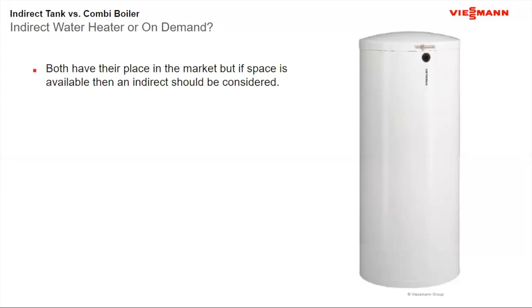Okay, so when we look at the indirect or the on-demand water heater, as I said earlier in the presentation, both types of water heater have their place in the market, but if space is available, then the indirect can be considered. And really, there are instances where the indirect does not make sense. Now, when I look at the indirect, a lot of the advantages, and actually some of the perceived disadvantages, are about the storage. One of the disadvantages is the footprint. If the space is available, when I do an indirect water heater, that is one more piece of equipment taking up space in the mechanical room along with the boiler.